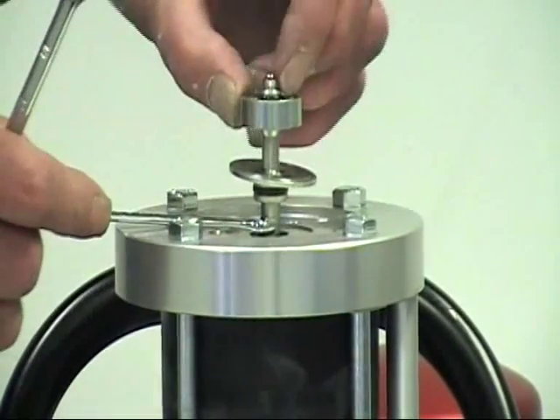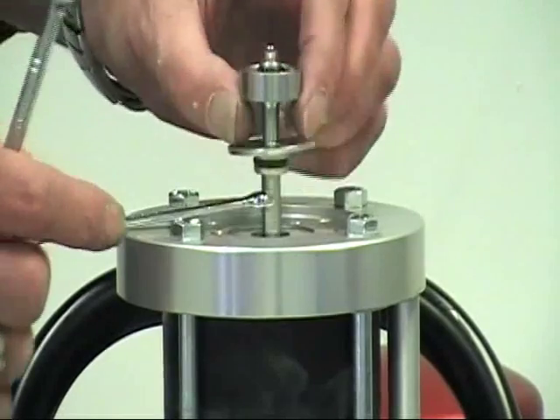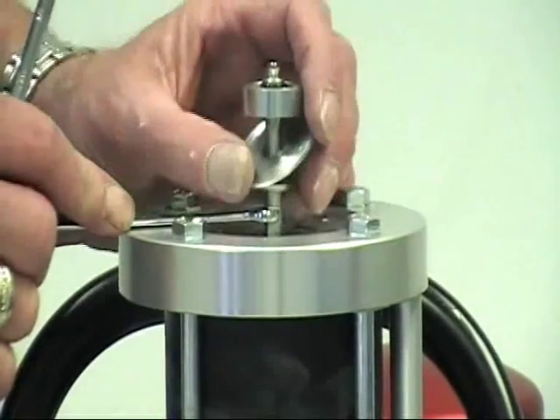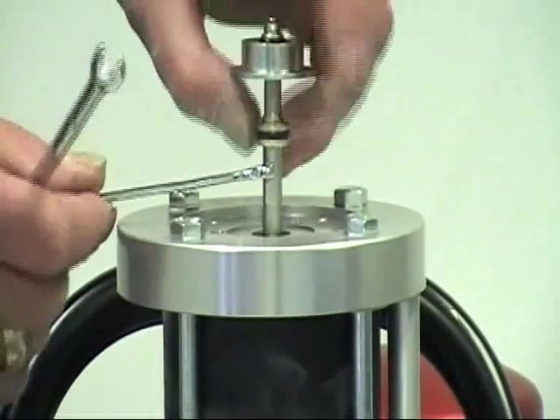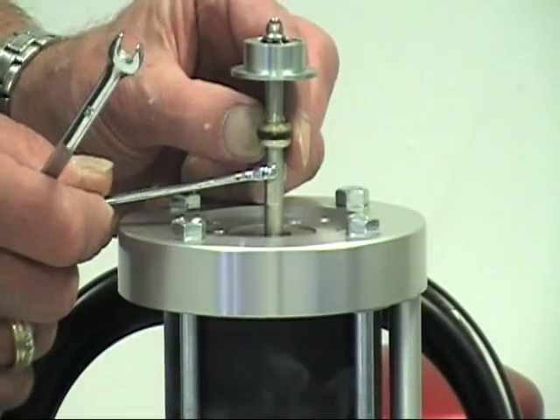If these are both tight, inspect the o-ring on the top of the magnet and the o-ring on the bottom of the magnet. On the circle piston, there is another o-ring. Make sure there are no cracks or breaks.